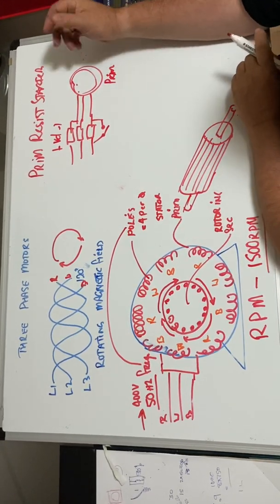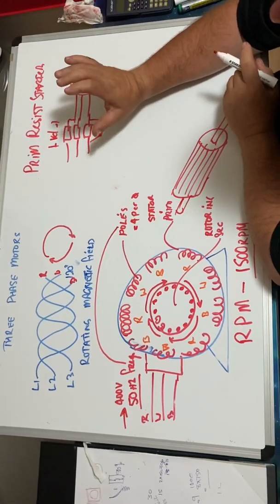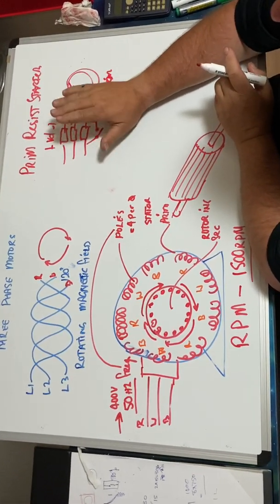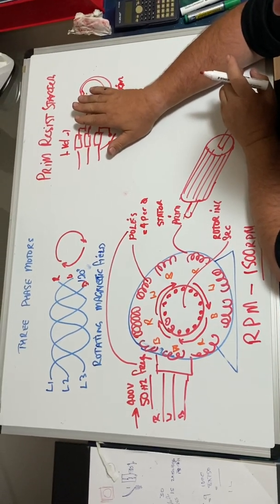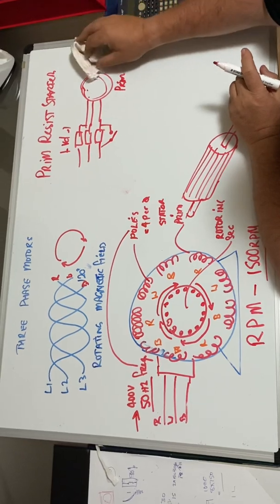The thing we have across here is voltage drop. This is what we call primary because it drops the voltage to the primary on the stator part, which is the stator of the motor. After about 20 seconds, these will change out, bridge the resistors out, and then create full voltage onto the motor. We end up with a voltage drop before it gets to the motor. That's called a primary resistance starter.